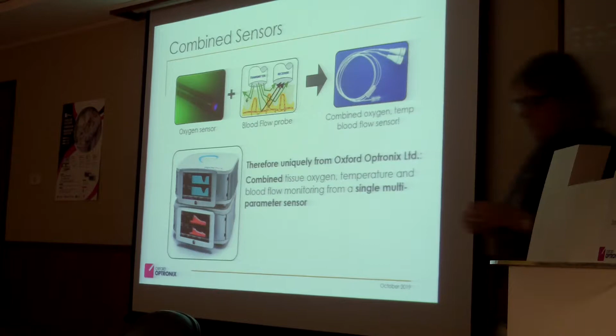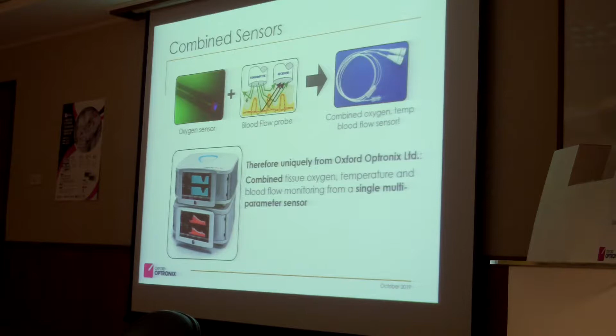Oxford Optronix is the only company in the world which offers a combined sensor, which measures oxygen and temperature and laser Doppler in one sensor. And the sensor splits at the end into 2 connectors which go into 2 different devices. So it's a very unique setup. It's very popular in rat brain research, for example, because the sensor is very small. You can target it to one spot and you don't have so many cables when you're working practically. Yeah. So this would be, we call them triple sensors, so that's oxygen, temperature, and laser Doppler. Yeah, it's a bit strong. So the red, you can see a red line, that's the thermocouple, which measures the temperature.